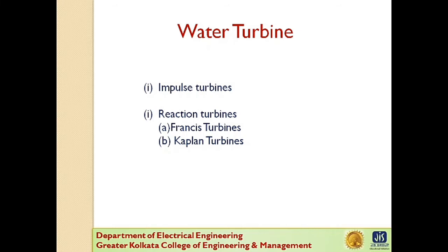Whereas the Kaplan turbine is similar to the Francis turbine, except that the runner of the Kaplan turbine receives water axially. Water flows radially inwards through regulating gates all around the sides and changes direction in the runner to axial flow. Now this causes a reaction force which drives the turbine.